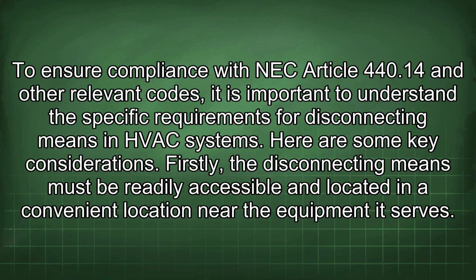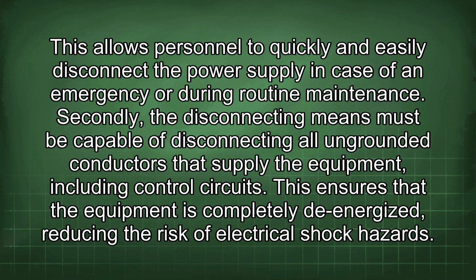To ensure compliance with NEC Article 440.14 and other relevant codes, it is important to understand the specific requirements for disconnecting means in HVAC systems. Here are some key considerations. Firstly, the disconnecting means must be readily accessible and located in a convenient location near the equipment it serves. This allows personnel to quickly and easily disconnect the power supply in case of an emergency or during routine maintenance. Secondly, the disconnecting means must be capable of disconnecting all ungrounded conductors that supply the equipment, including control circuits. This ensures that the equipment is completely de-energized, reducing the risk of electrical shock hazards.